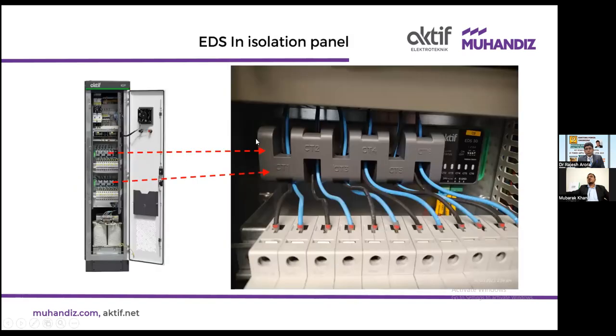So this is an insulation fault location device which sits in the panel. The CTs are molded together, 6 CTs, and all the outputs of the circuit breakers pass through the CTs in a core balance. As you can see, phase 1 and phase 2, both conductors, are passing through the CT itself. So it is a core balance CT.